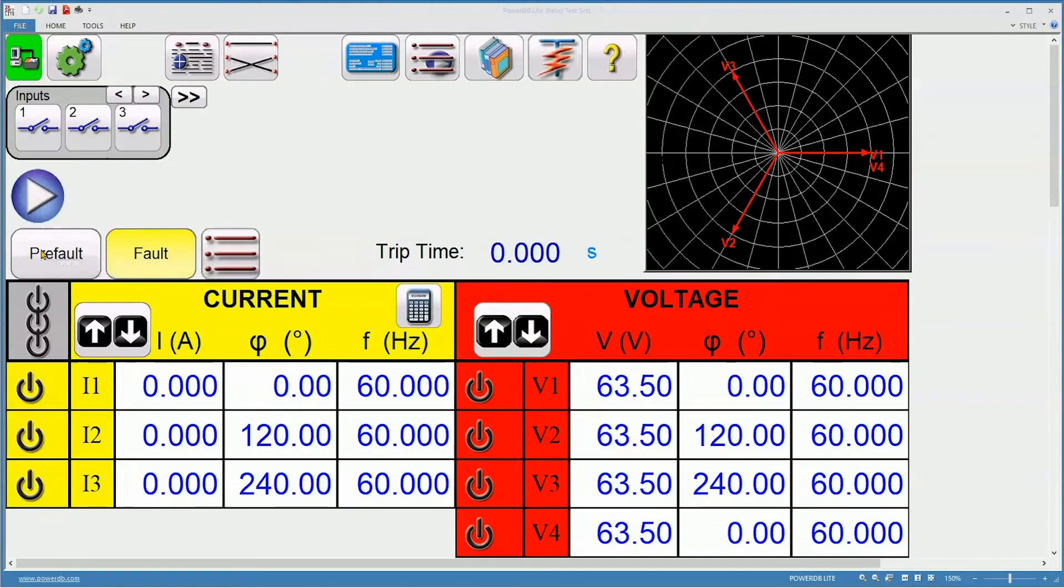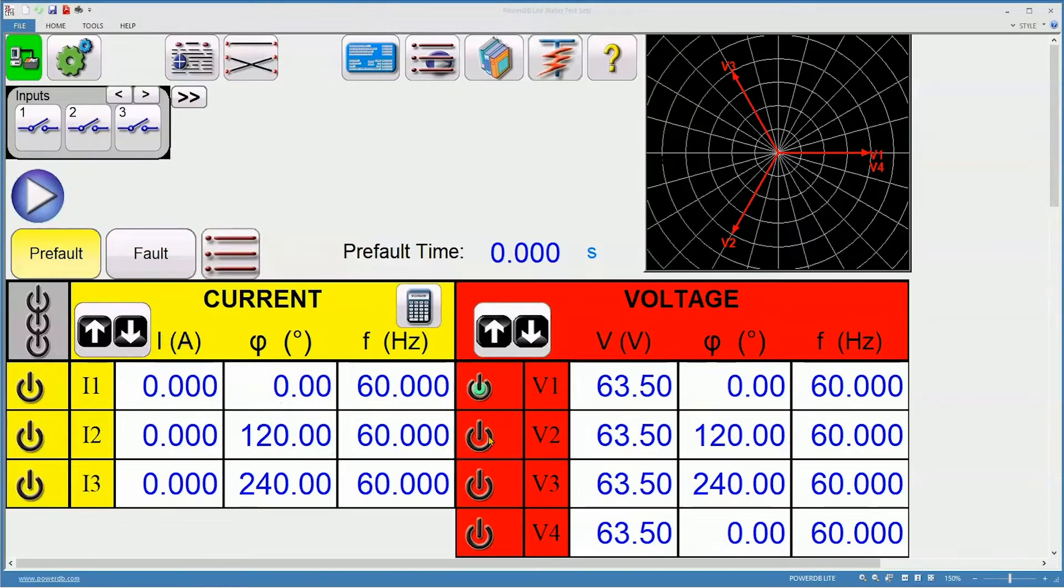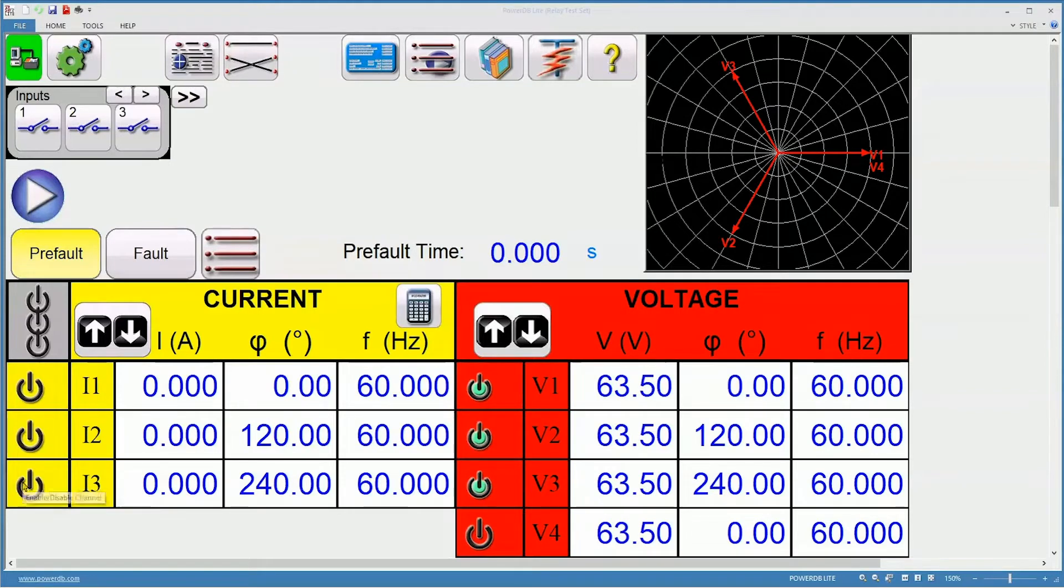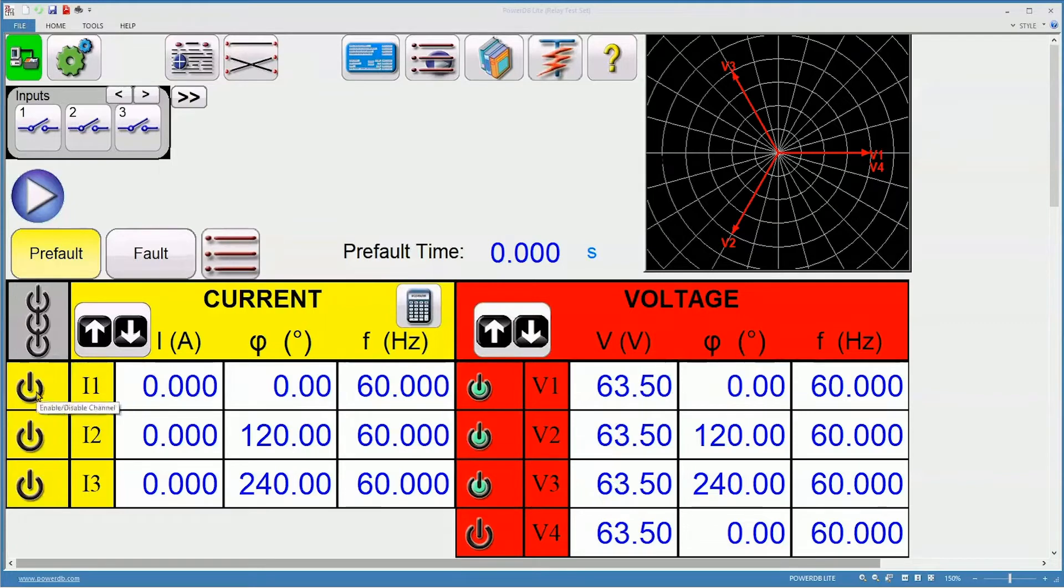Pre-fault. Some relays need to have polarizing voltage or possibly a stabilizing current applied prior to the test. I've turned on three-phase nominal voltage, and I'm going to turn on three-phase at one amp as a pre-fault value.